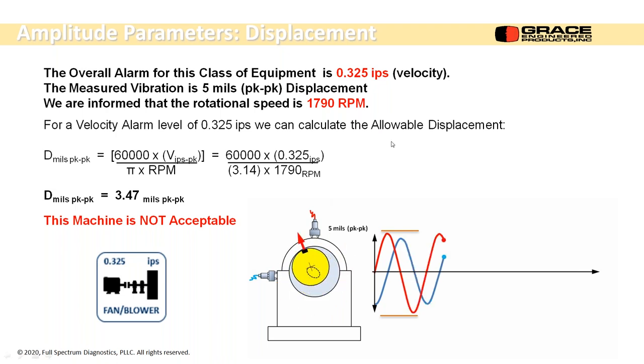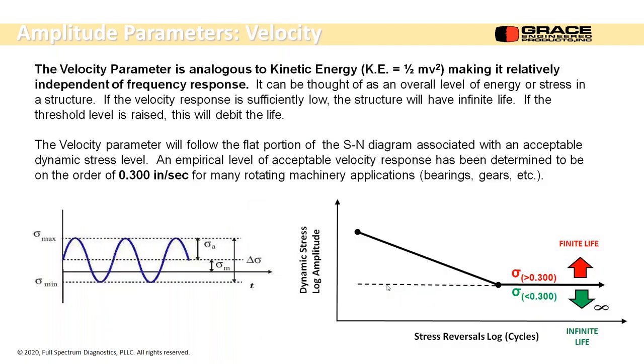Now, if he said we have 8 mils of vibration, I'd have to go back in with the same information and calculate what the allowable displacement limit is based on the velocity for 8 mils and find out if that's good or bad. And it's going to be bad again. Okay. Now, this is the roundabout way. I just wanted to get it through your head. This is variable. So the displacement amount isn't enough. You have to tell me what frequency we're talking about so that I know where I am along this curve and what's allowable.